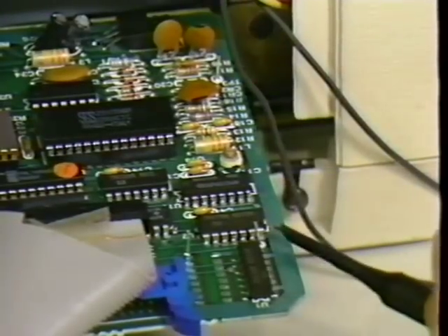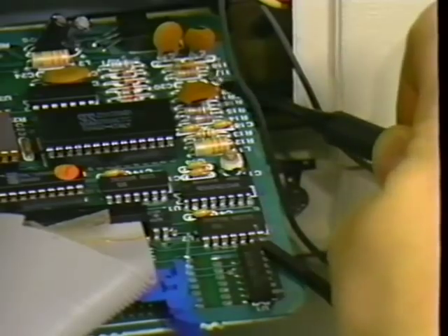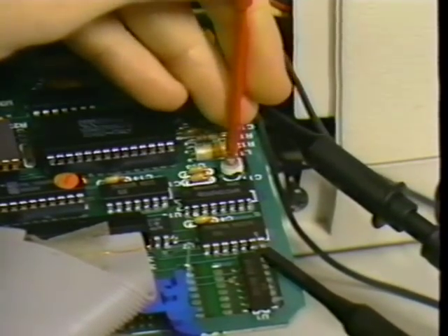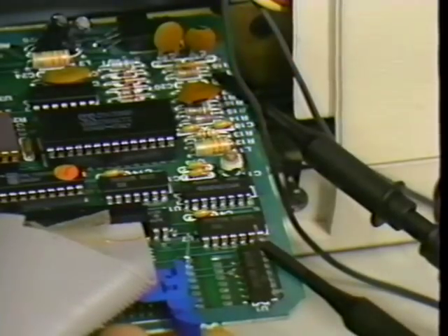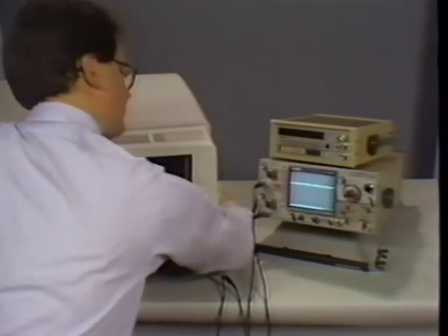Now, turn the unit off and return the test jumper to its normal position. Power the unit back on and adjust the VCO as described in the manual. This alignment is very similar to that on the 8X300 board. Channel A monitors the VCO's output frequency and Channel B its input bias. On this board there is no potentiometer, only an adjustable capacitor. Align it so that the VCO frequency is directly on specification and the DC bias is as close as possible to the center of its range. As on the 8X300 board, turn the unit off and back on to verify that the VCO locks properly.